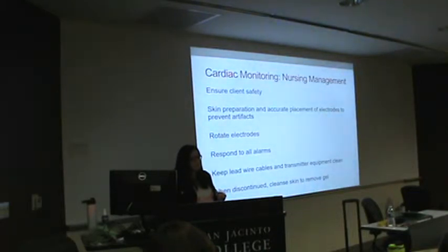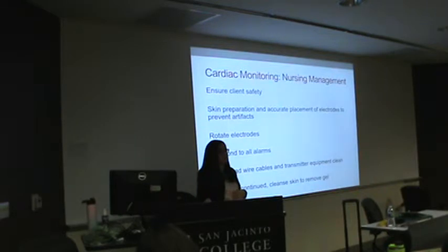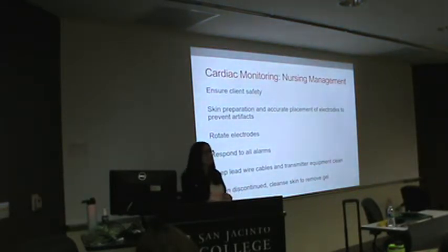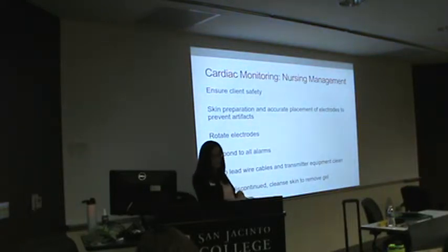Because what happens is, have y'all heard of alarm fatigue? They get desensitized, right? Am I saying that word right? Desensitized. So it takes them a longer period to respond sometimes, and this could be fatal for our patients. Or they may miss some important alarm. They probably think it's the battery, and they'll do it later. So just pay attention to that, okay? And always keep in mind client safety, because that desensitization does happen with overexposure to frequent calls or alarms. Keep lead wires, cables, and equipment all clean.